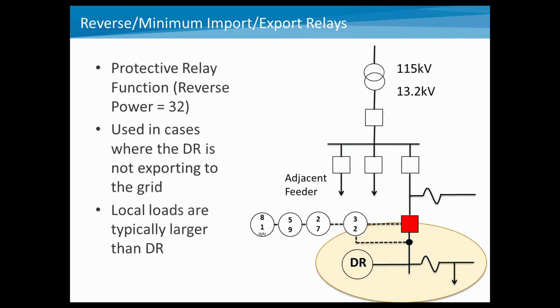So first off, taking a look at things like minimum or reverse import-export relays. What that means is they basically set a relay. If you look in the figure where that red box is the breaker, you may have some relay functionality attached to it. These numbers, 81, 59, 27, and 32, are relay functions. 32 is reverse power, and in this case, if the power is ever reversed onto the utility grid, that would trip that particular breaker. This is for what utilities typically call a non-export condition, and if you're set to never inject power back onto the grid, this is typically used for that case. Now, a lot of times, this is when you have a large local load.